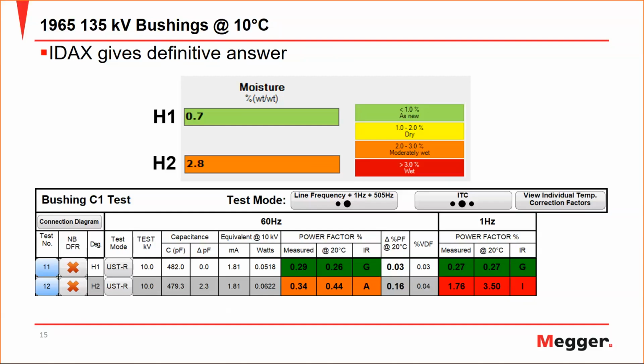Is it okay if I also talk a bit about this? Ole Bensler, I spoke yesterday as a presenter. For the dry types, sometimes they're shielded between the primary and secondary side. So then you would focus more on the ground measurement, because with the UST measurement you will only see the shielding between the two windings. It's also important to point out that the tangent delta of this type of power transformer might change a bit with time, because the core gets more settled into its structure over time. When you measure after the factory, it hasn't been fully solid yet, so as time goes on, the value will change a bit. I don't think you normally perform the partial discharge test for these types of transformers to look for cracks in the insulation.